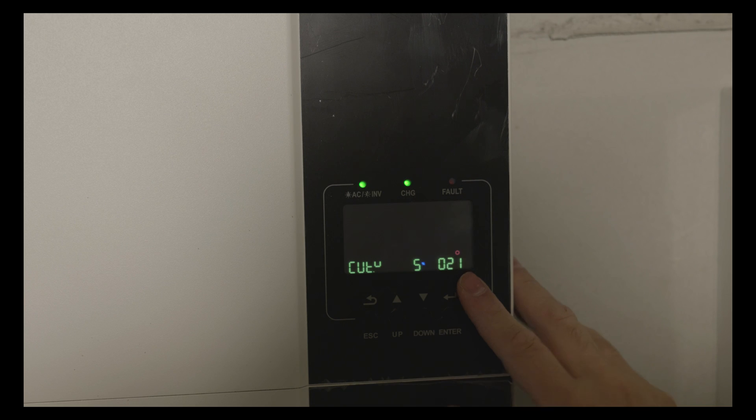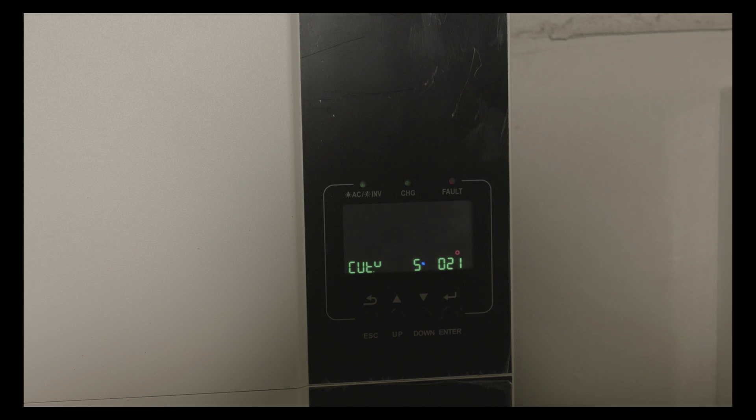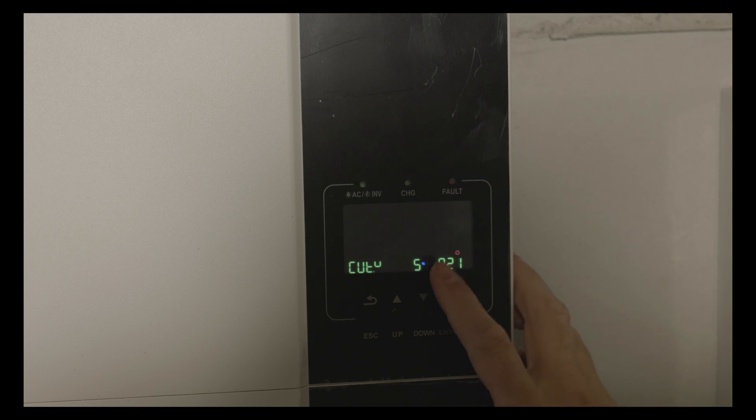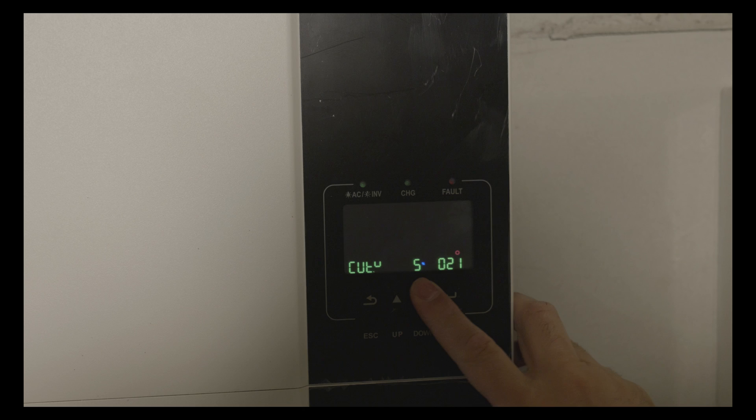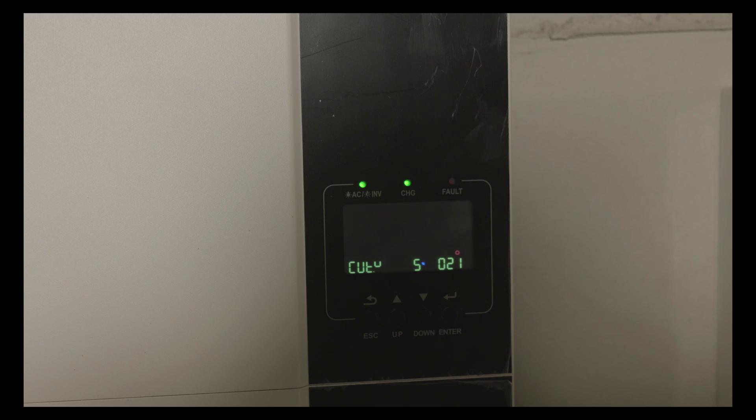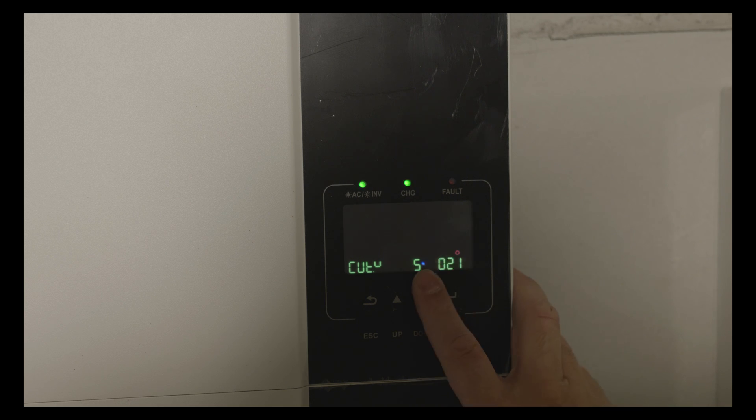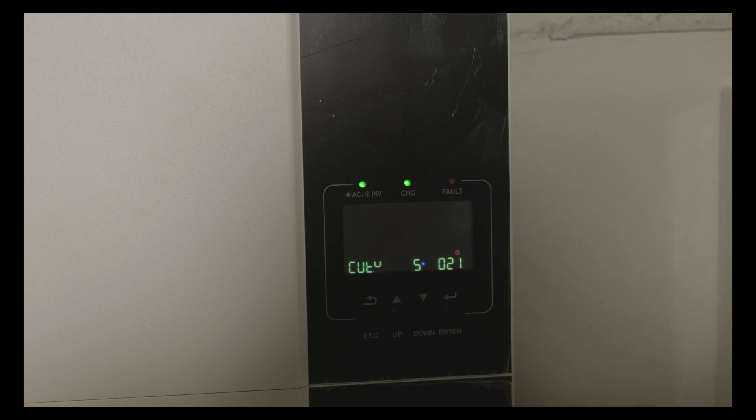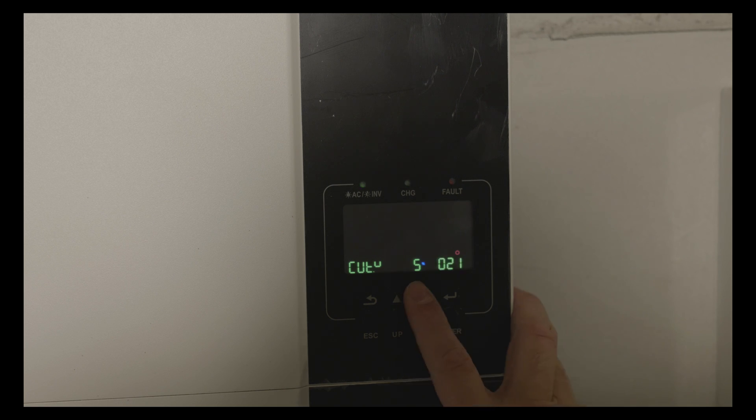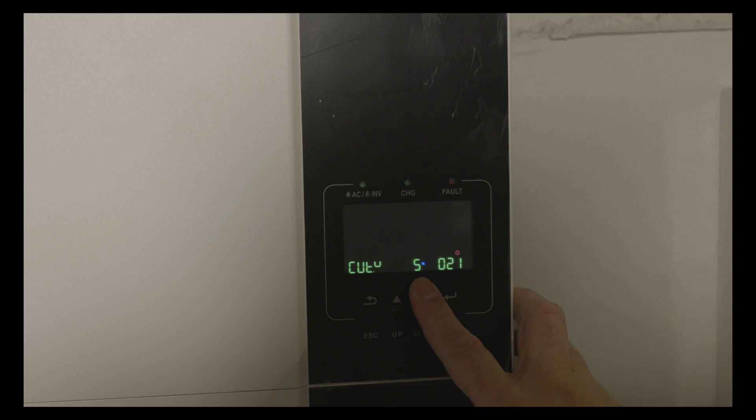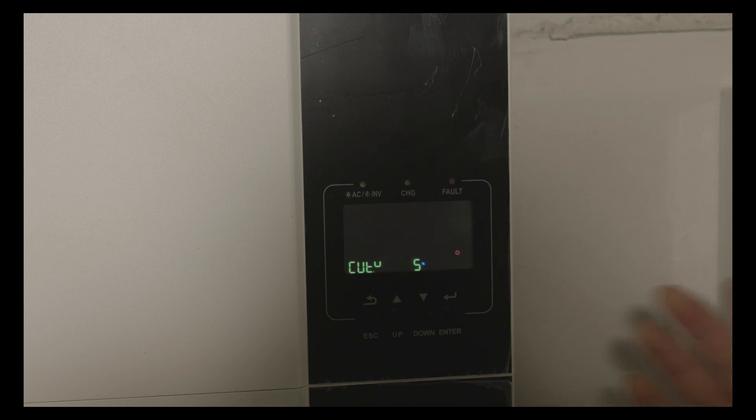This option is for low DC cutoff voltage. This means that when the batteries hit 5%, the system will shut down. If you're using USE option in the battery type this will be in volts, so it depends on what battery you have. For lithium it's like 42 volts, but just in case you can set it like 44 volts or 43 so you don't drain the batteries to zero.